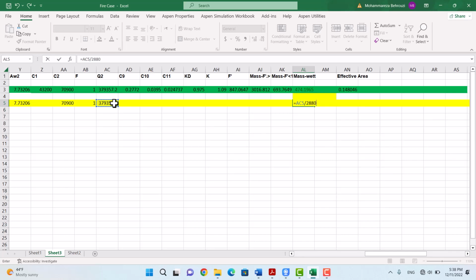If I do these calculations, I'm not going to get the relief load in kilogram per hour. So I have to take into account the conversion between kilojoule and watt, which is this value. So the relief load here is this value.